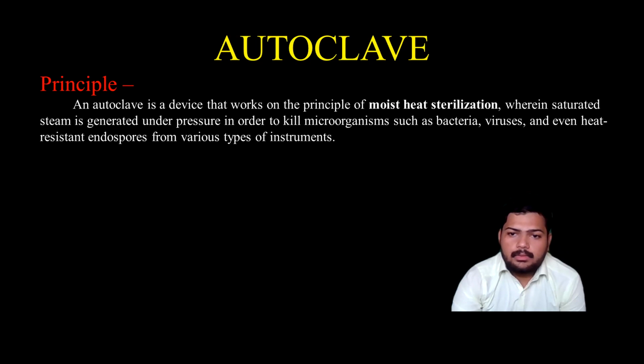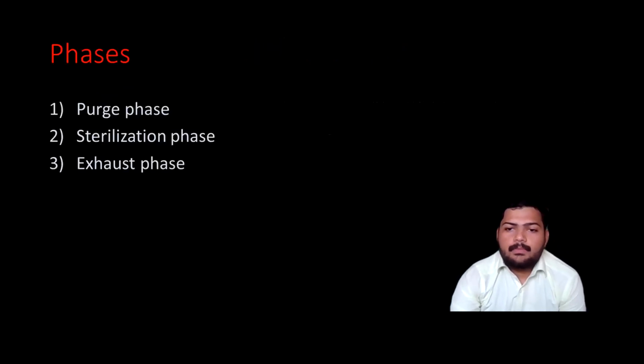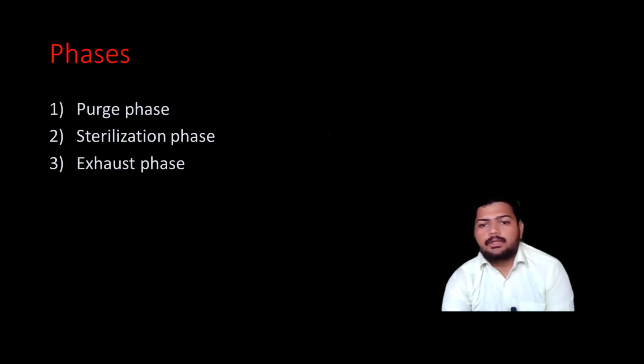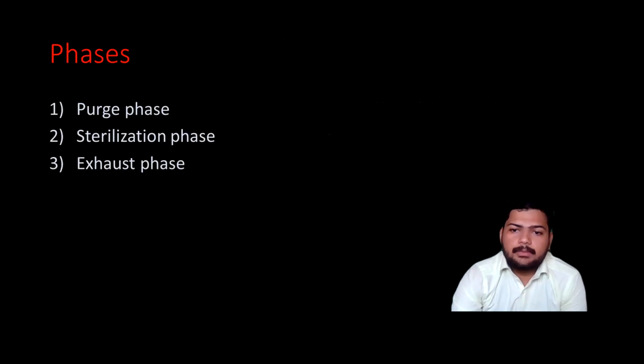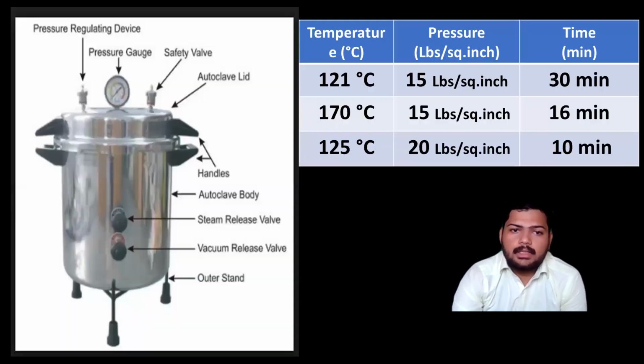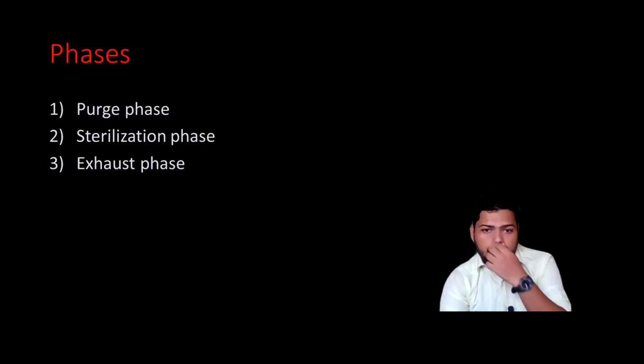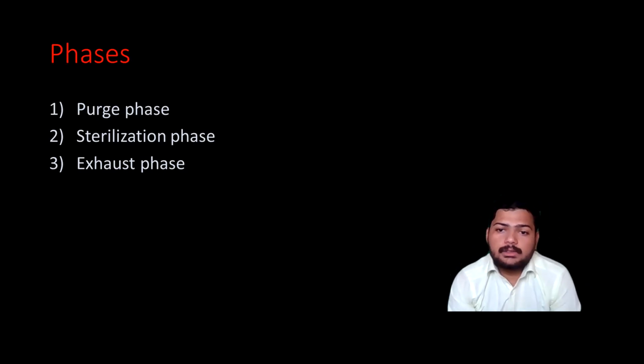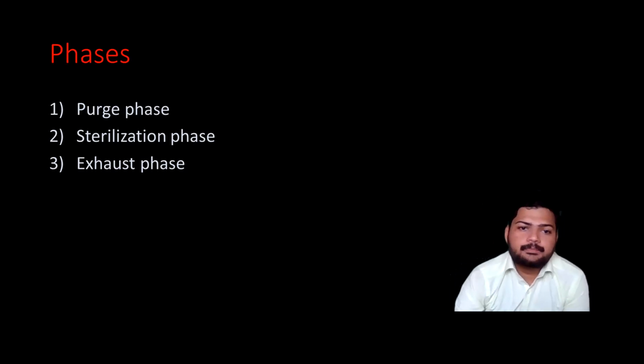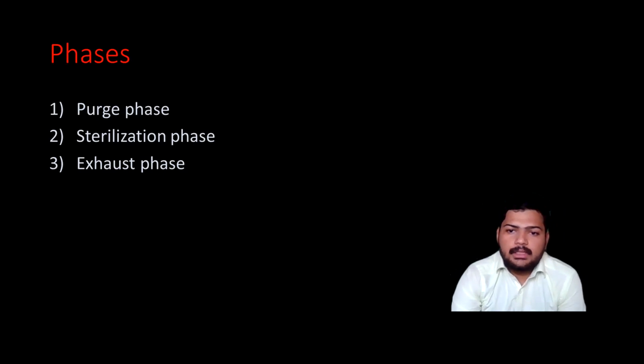So there are three steps to autoclaving. First one is the purge phase, in which steam is introduced into the autoclave, so that temperature and pressure are gradually increased. In the sterilization phase, due to the increased pressure and temperature, and also because the exhaust is closed, the bacteria and viruses are killed under such harsh conditions. In the exhaust phase, the steam is released, due to which the pressure is reduced, but the temperature remains high, so we have to take care when removing the lid and taking out the hot contents. We have to use gloves to do that.